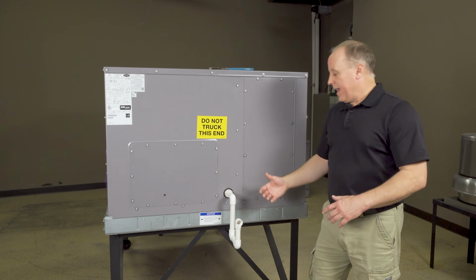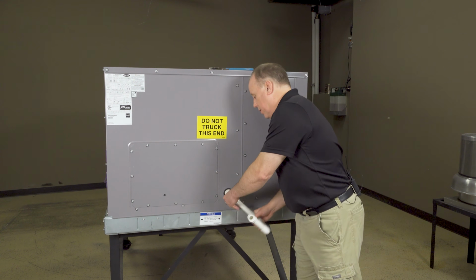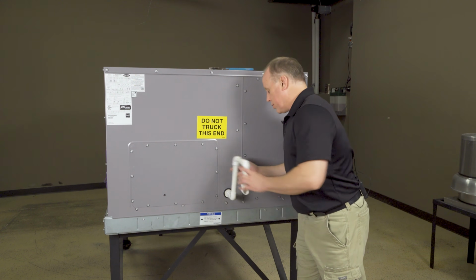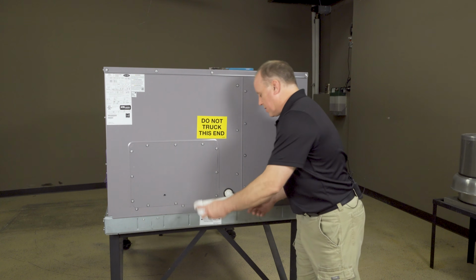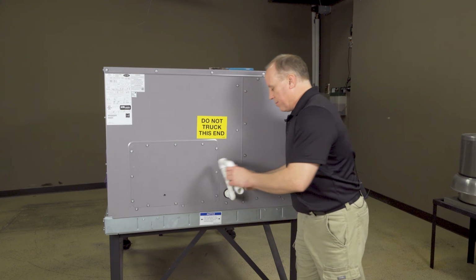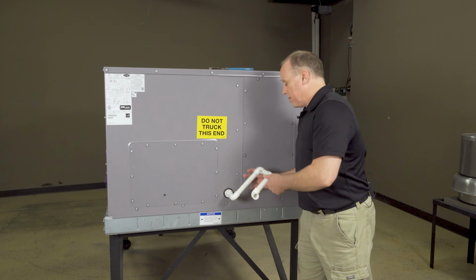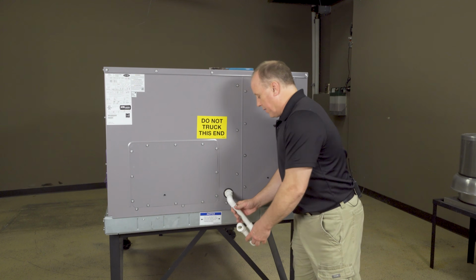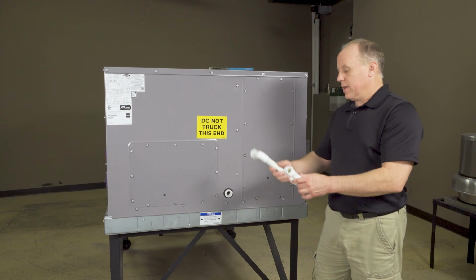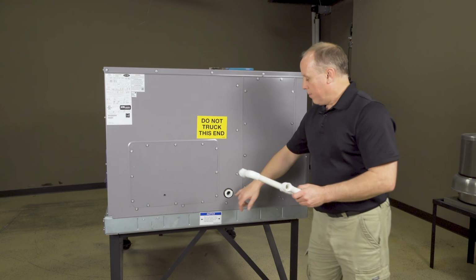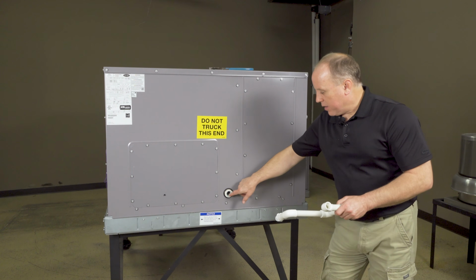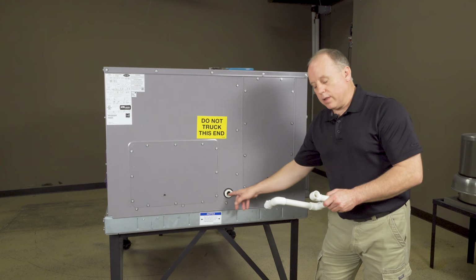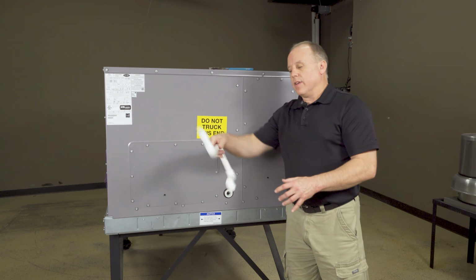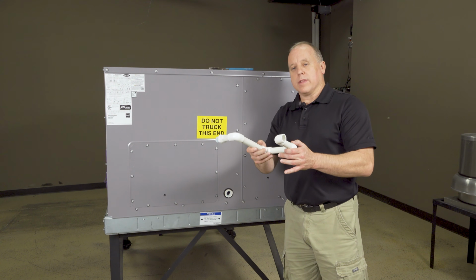So to clean that out, generally all we're going to do is twist this off. It's just screwed in. In a lot of cases it's going to be 3/4 PVC fittings. It may be metal pipe, just depending on how it was installed. Traps could be different sizes and configurations. We're just going to take that off. We can make sure our immediate fitting on the unit doesn't have any debris in there. We could clean that out, and then we could dump this out. We could also flush it out with a hose.